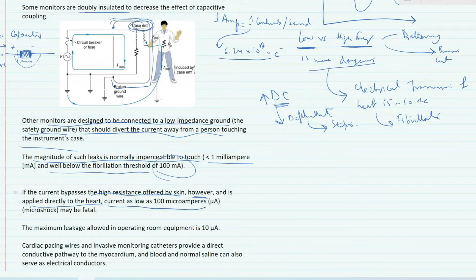The magnitude of such leaks is normally imperceptible to touch - as low as 1 milliampere, well below the fibrillation threshold of about 100 milliamperes. But if the current bypasses the high resistance offered by skin - if there's a breach of skin, or invasive lines, and current is directly applied to the heart - current as low as 100 microamperes, called microshock, may be fatal and could cause fibrillation.